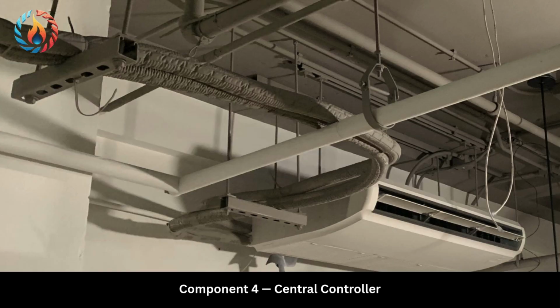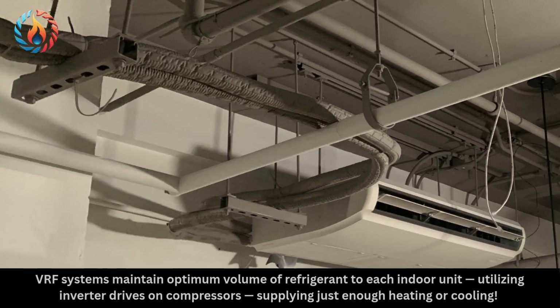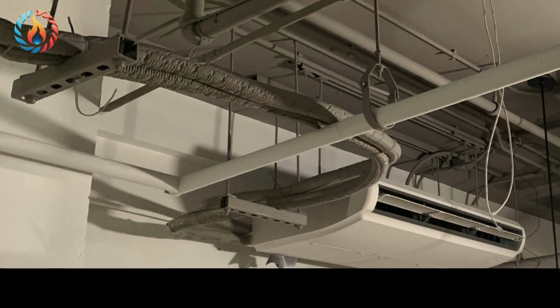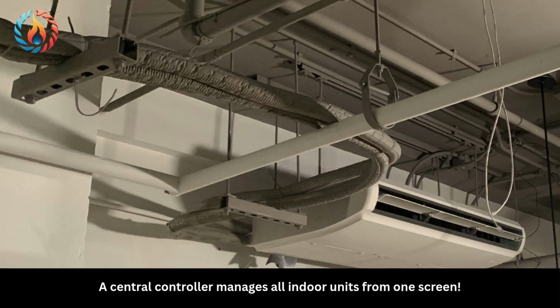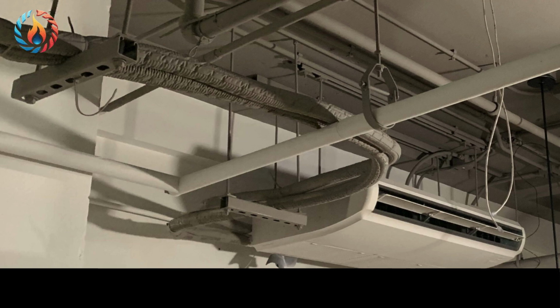Component 4, central controller. VRF systems maintain optimum volume of refrigerant to each indoor unit, utilizing inverter drives on compressors, supplying just enough heating or cooling. A central controller manages all indoor units from one screen. Building managers can control the entire system from one place, set schedules, monitor temperatures, check energy consumption.